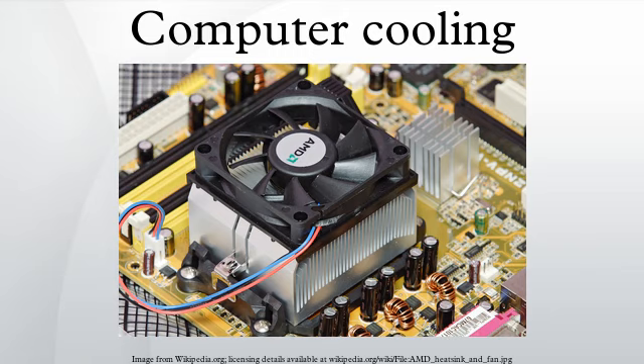Parallel versus series installation. Fans can be installed parallel to each other, in series, or a combination of both. Parallel installation would be fans mounted side by side. Series installation would be a second fan in line with another fan, such as an inlet fan and an exhaust fan. To simplify the discussion, it is assumed the fans are the same model. Parallel fans will provide double the free airflow but no additional driving pressure. Series installation, on the other hand, will double the available static pressure but not increase the free airflow rate. The adjacent illustration shows a single fan versus two fans in parallel with a maximum pressure of 0.15 inches of water and a doubled flow rate of about 72 cubic feet per minute.